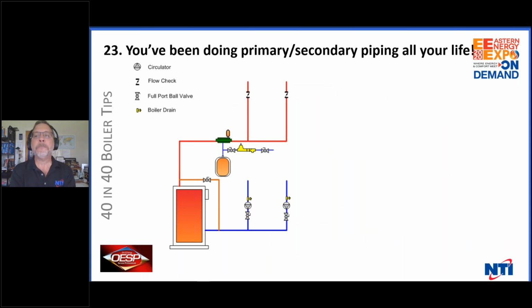Primary, secondary piping, you've been doing it all your life. When we used to take those huge cast iron boilers out and put in little teeny weeny 68 series Weil-McLains, right? It's pretty funny. You had these 3 and 4 inch gravity mains, and all that cold water was coming back, and it was coming back to that back section and warping it and making the nipples or the rings leak or cracking the back section. It was horrible. So how do we get around that?